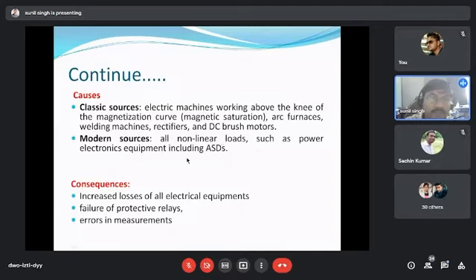What are the causes of these harmonics? There are two types of causes. The earlier, or conventional, causes are electrical machines working above the magnetization curve, meaning saturation, arc furnaces, welding machines, rectifiers, and DC drives. So these are our conventional sources of the harmonics.